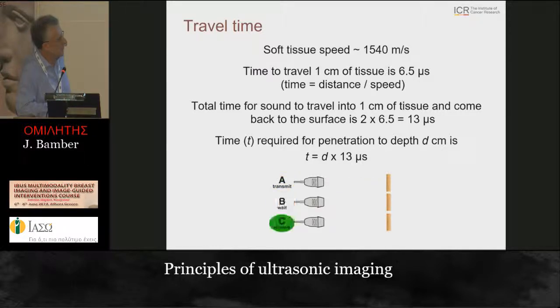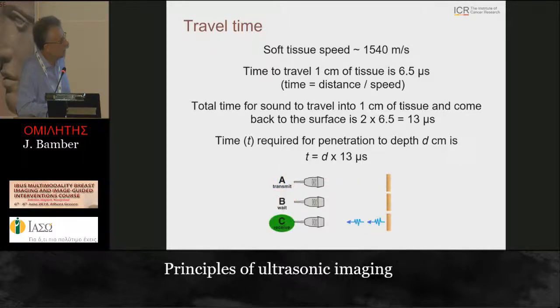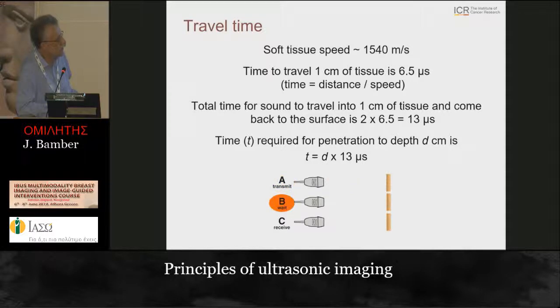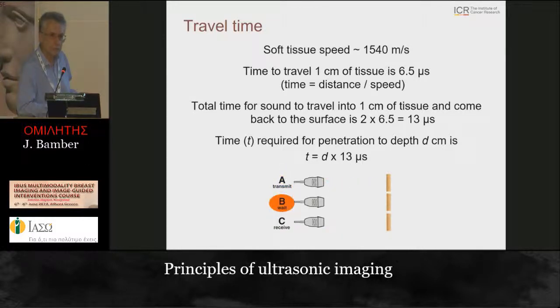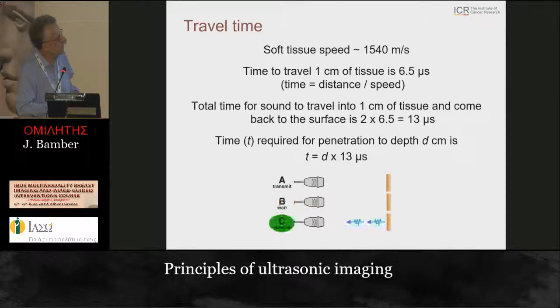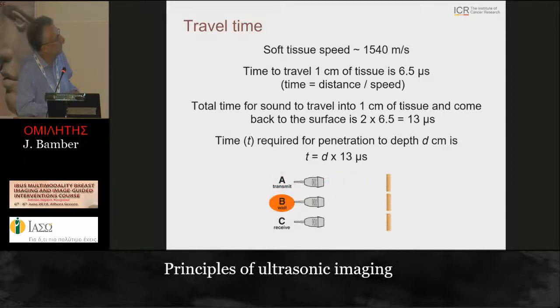Due to the speed of propagation of ultrasound, there is a limit to the combination of imaging depth, number of lines, and frame rate. When you transmit a sound pulse into the tissue, it has to travel to the depth of interest where it gets reflected, and then you have to wait for that reflection to come back before you can display the echoes. The total travel time to that depth and back determines the line rate.